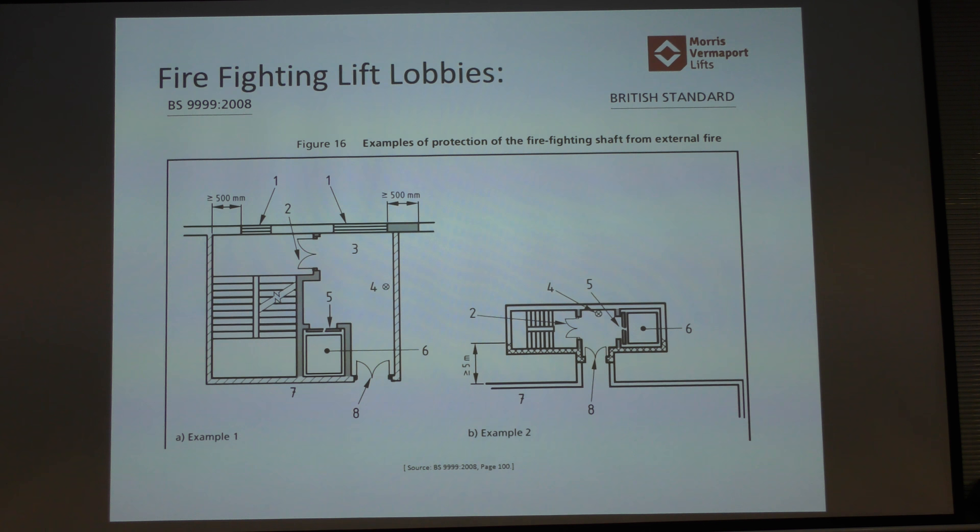If you can't do the grating, or if the lift lobby is the sump in the pit — the sump in the pit is an absolute requirement anyway, because any water ingress that gets in needs to be pumped out so the pit doesn't fill up, as there are pit switches and electrical components in there. Ramping is the simplest option: just lift the doors up a couple of inches to try and stop that water ingress.